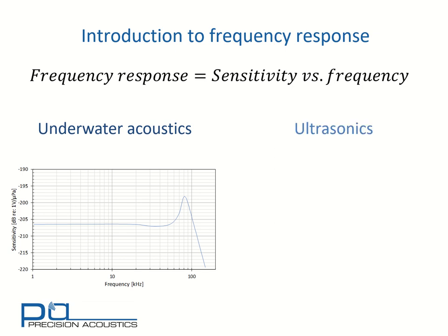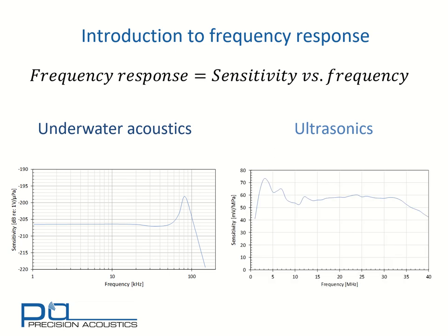In contrast, in ultrasonics, where hydrophones are typically larger than the wavelength being measured, we can find very much more variation in the frequency response. We'll go on to consider this in a little more detail.